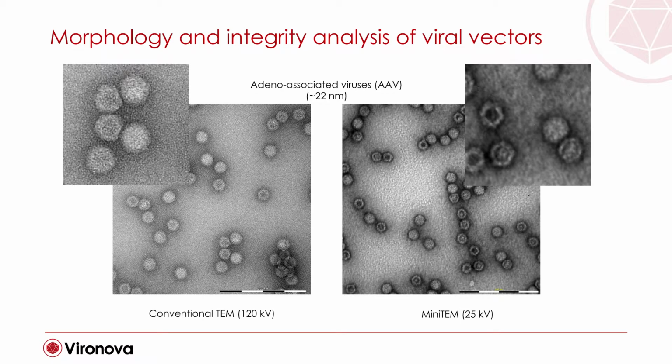If we go a bit further in high magnification, we can see that the MiniTEM shows some limits when it comes to resolution. The morphological features can be seen in both techniques, but the images are a bit less crisp using the MiniTEM. We are aware of this limitation, but still, for this particular application, all the information required by the user is given by the system.